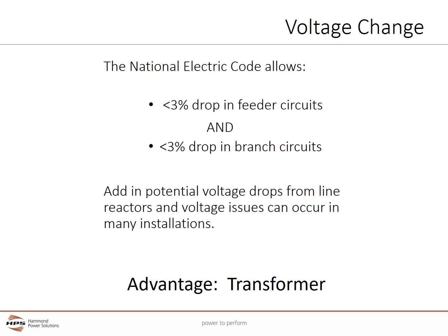The National Electric Code allows for a 3% voltage drop in feeder circuits and another 3% voltage drop in branch circuits. This is on top of the voltage drop a line reactor can cause. The taps on a transformer can often accommodate for this and adjust the voltage back up. Even though reactors can cause voltage drops, it is still highly recommended in most cases where the voltage allows to install at a minimum a line reactor with a VFD. However, in this case, the advantage is still with the transformer.